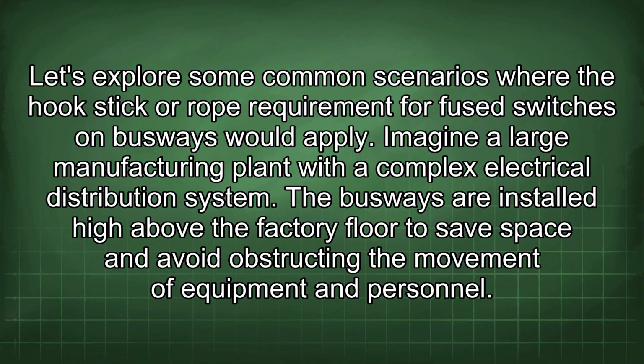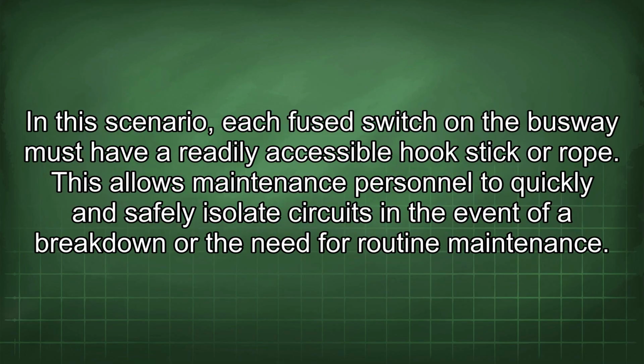Let's explore some common scenarios where the hook stick or rope requirement for fuse switches on busways would apply. Imagine a large manufacturing plant with a complex electrical distribution system. The busways are installed high above the factory floor to save space and avoid obstructing the movement of equipment and personnel. In this scenario, each fuse switch on the busway must have a readily accessible hook stick or rope, allowing maintenance personnel to quickly and safely isolate circuits in the event of a breakdown or the need for routine maintenance.